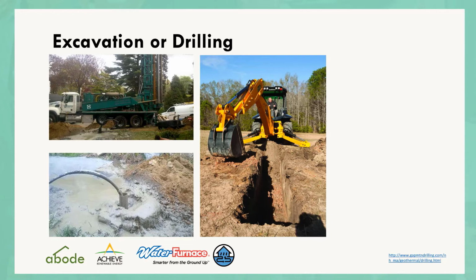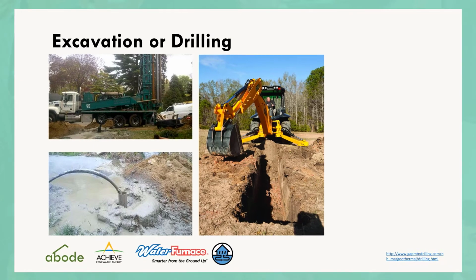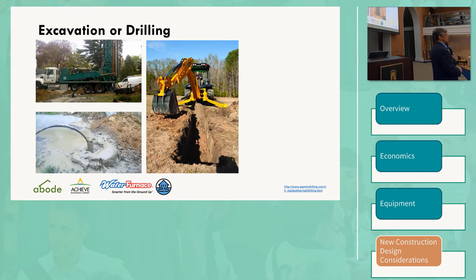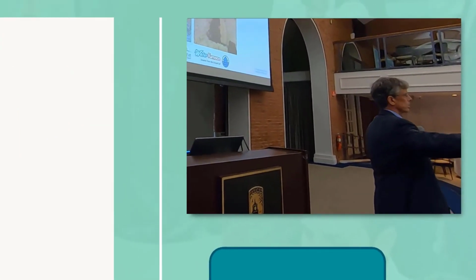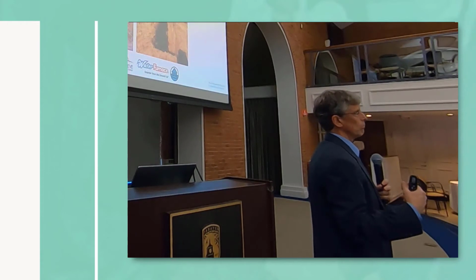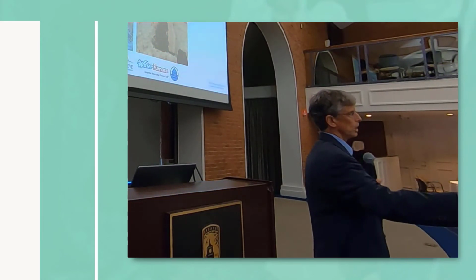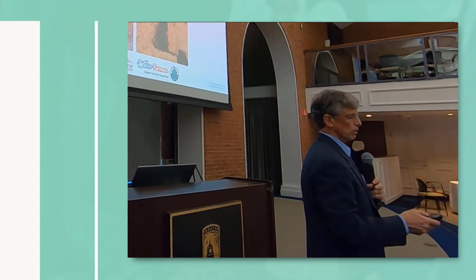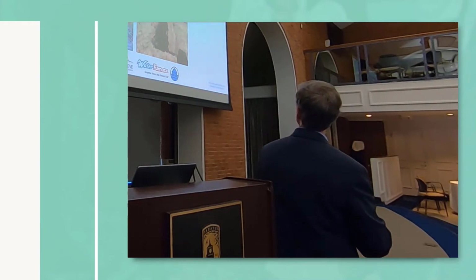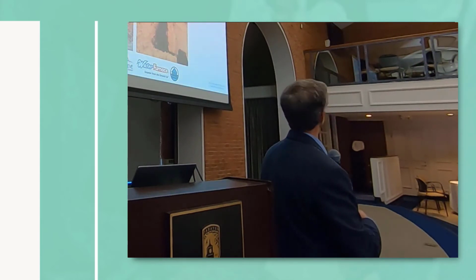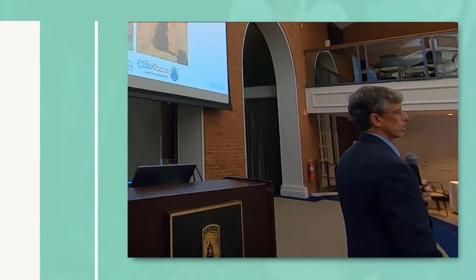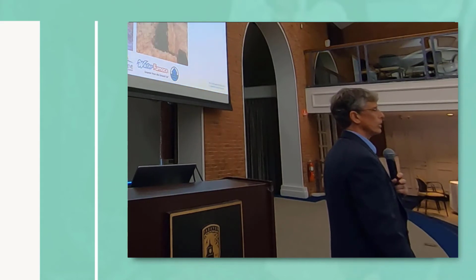Horizontal loop systems are also possible, and you can do that by excavation, but you need a relatively large area. Normally, trenches for geothermal are about 3 feet. Depends on what piping configuration. You're going like this. So the slinky configuration, where the piping looks like a slinky that's been pushed out flat, would normally be 1 ton of capacity is a 3-foot by 100-foot trench. And those are 10 feet on center. So 4 tons of capacity would come out of 2 borings to 300 feet each, or 4 100-foot trenches 10 feet apart, so a 100 by 30-foot area, or actually more like 40 feet because the trenches have some width to them.